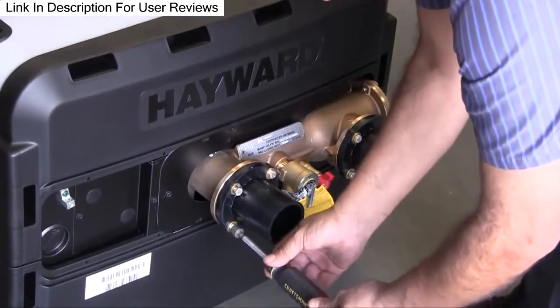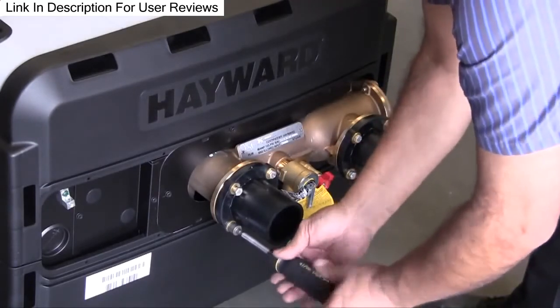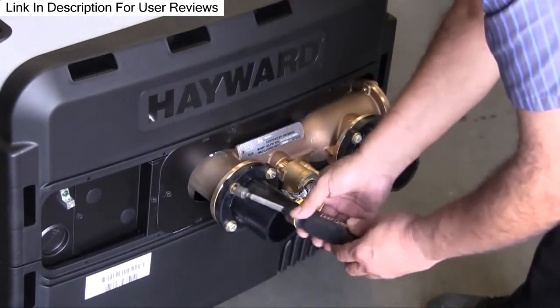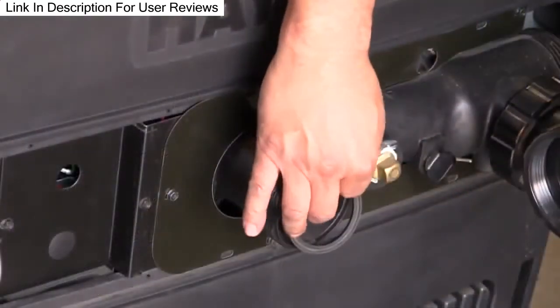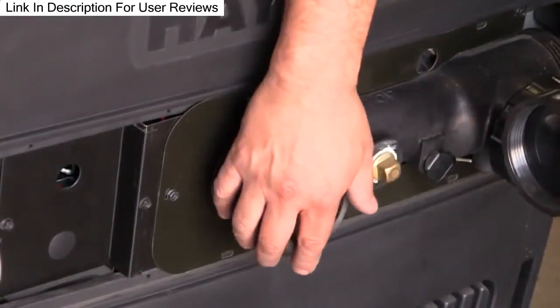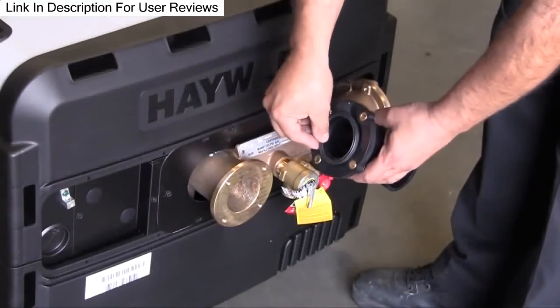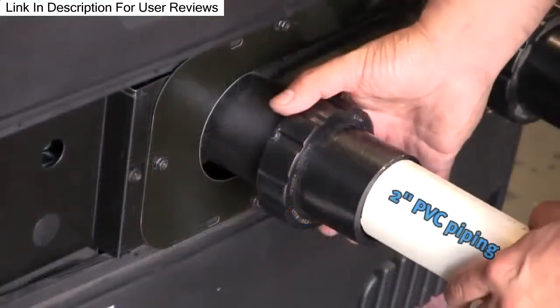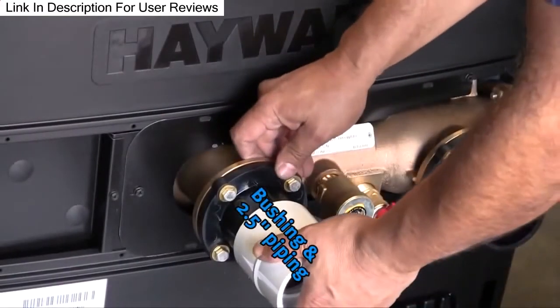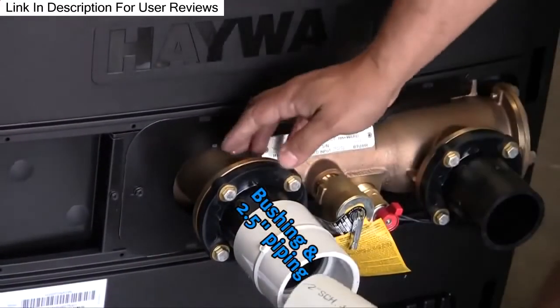It can be difficult to align unions for tightening if they are glued to the pipe before connecting to the heater. Make sure the seals are in place on the header for the residential heater and on the flange for the commercial heater. Both fittings will accept either a 2-inch pipe or a bushing, allowing the nipple to accept 2.5-inch pipe.